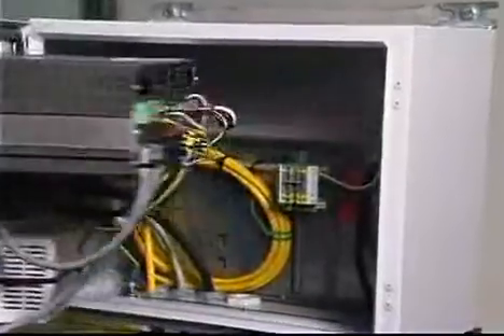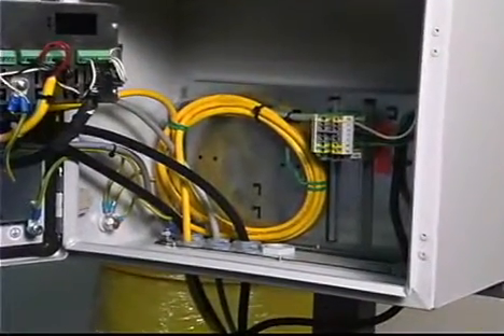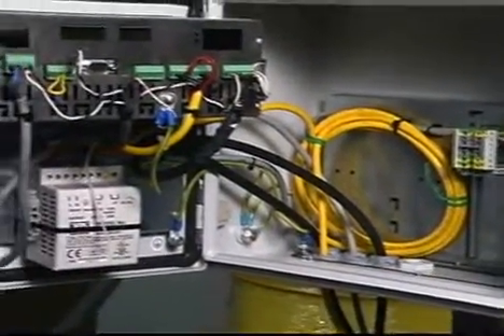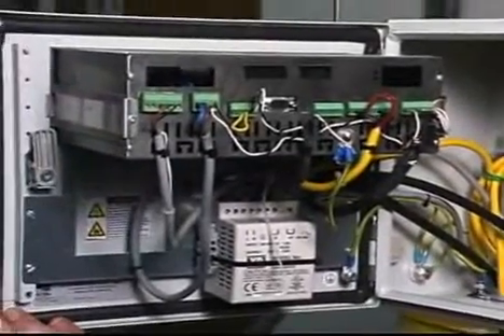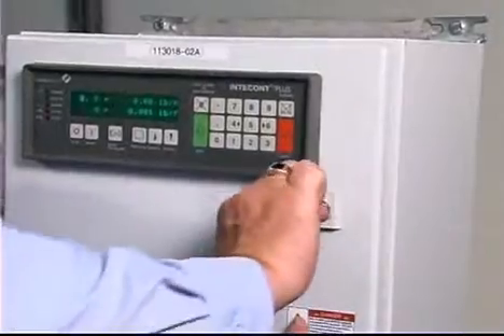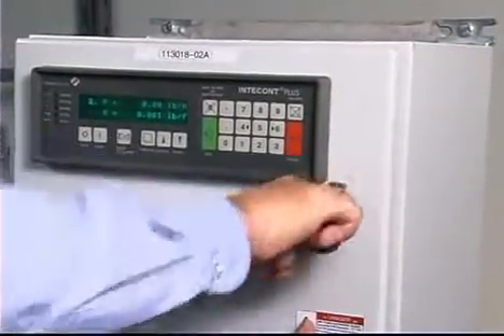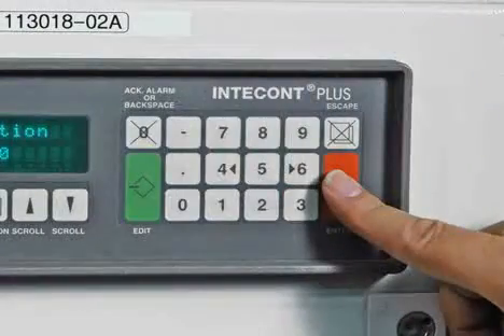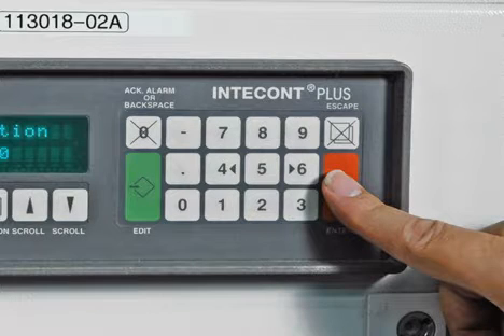Before calibration and setup can begin, the system hardware must be properly installed. The controller must be wired into the system, supplied with power, and fully functioning. The main activity is measuring and calibrating the parameters of the physical device, then entering this data into the software using the keypad and the LCD screen.